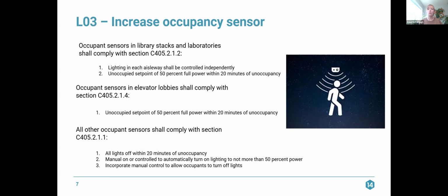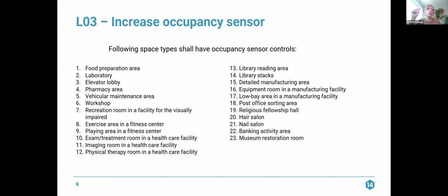The lighting is manual on or controlled to automatically turn on to not more than 50% power. And then you have to incorporate the manual control to allow occupants to turn off lights. So that's the increase for occupancy sensor. And you must, all of your building area, every space type, let me say that one more time. If you have elevator lobbies on every floor of your building, all of them have to comply to achieve credits. There is no prorating for the increased occupancy sensor credit.